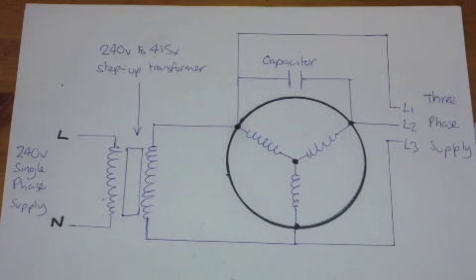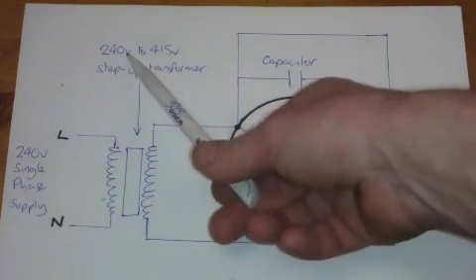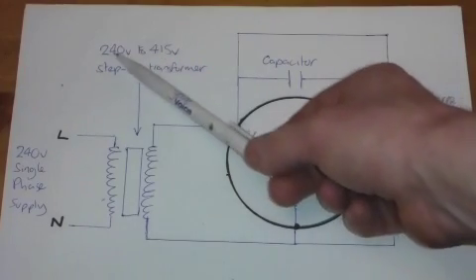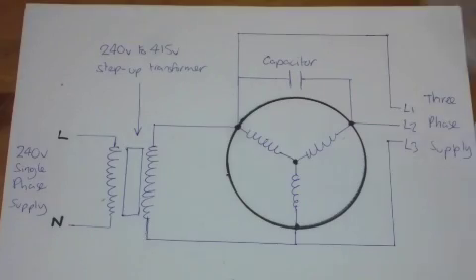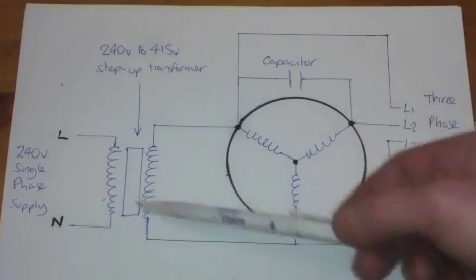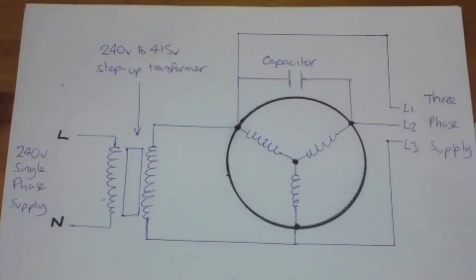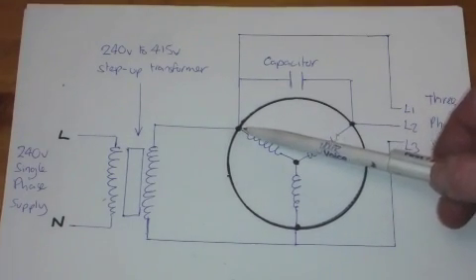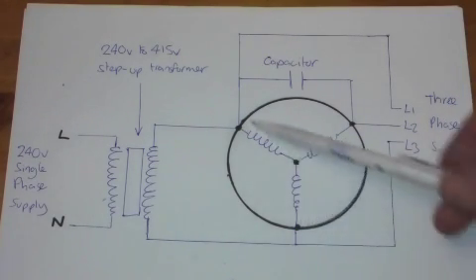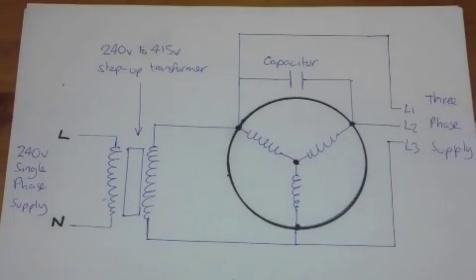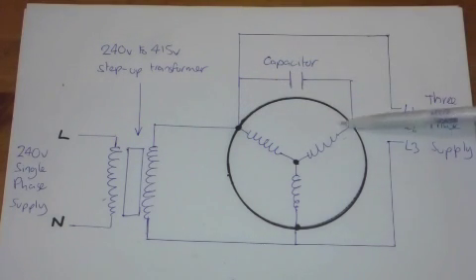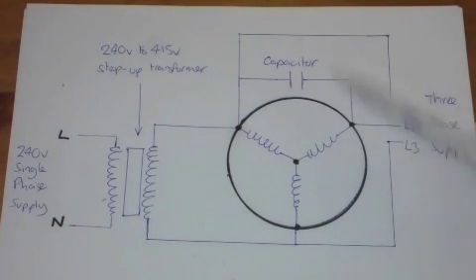Okay we're getting somewhere near now. This is the next development of the rotary converter and the difference between this and the last one is of course there is a step up transformer which increases the single phase supply from 240 to 415 volts. So there's the single phase supply it goes into a step up transformer so that increases the voltage here to 415 volts and goes on to one phase of the live and another phase of the neutral therefore we have the correct value of 415 volts between two phases marvelous from the live phase there is a capacitor that goes to the third phantom or false phase.